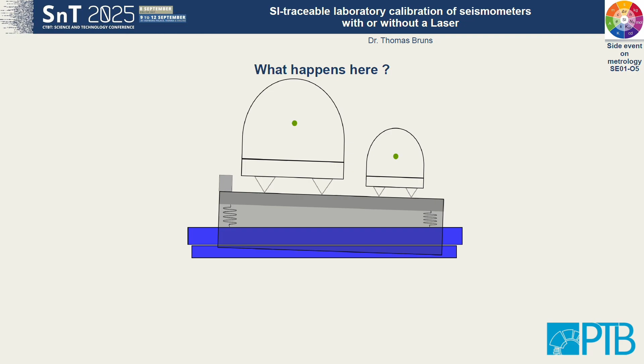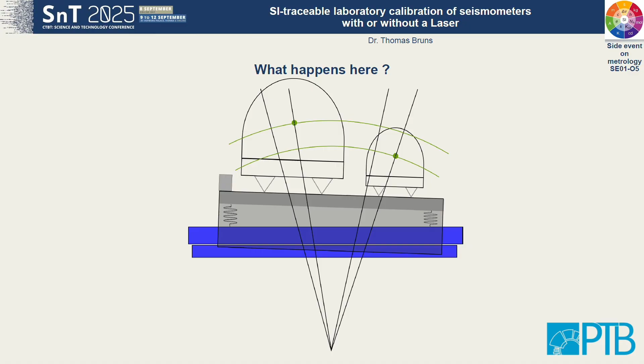So what is the influence that we have there? In the comparison calibration, if we use two different types of instruments, we have two different trajectories that they are following. If you consider the green point in the center to be the sensitive center, the spot or the height where the seismometer actually detects the velocity with its internal spring mass and feedback system, they are following different trajectories. They have different velocities that they are sensing, so you cannot compare these sensitivities directly. You have somehow to take this into account, and you can do that if you have the proper information.